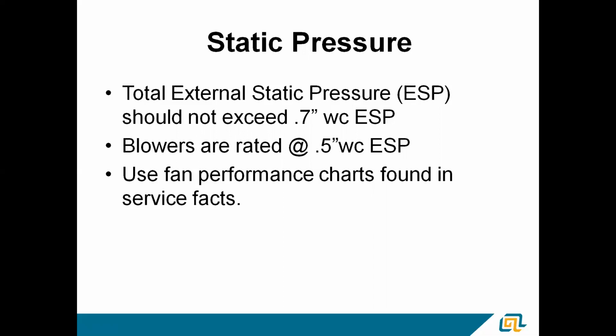Fan performance charts are found in Service Facts. I find them very useful. On the heating side, they even have expected temperature rise based on the amount of airflow you've got. So it's a good little thing to have. Sometimes they're not with the furnace, but if you don't have access to Comfort Site or AS Dealer Net, and you can't pull up the book, you can always give me a call and I will certainly find it for you.